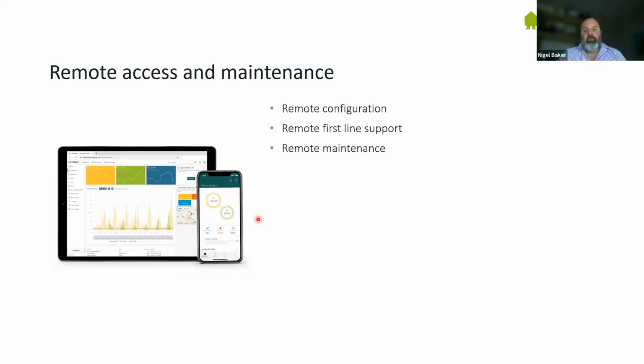So you don't need to go back to site to correct the installation. We want people to go to site, do the installation, walk away, and get accurate data. If for some reason the contractor doesn't do the installation correctly, you can remotely go and do the commissioning. I don't actually know of any other product that can do that, and that's one of the big pluses of the Smappee system—fixing an installation remotely. You can go map a phase and change a CT.